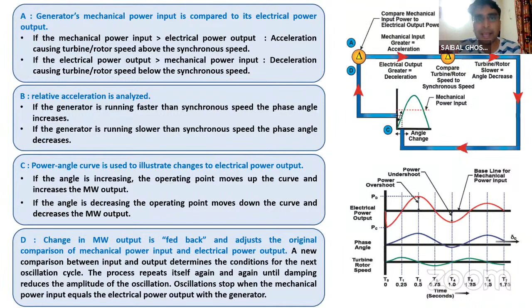At a certain point of time, electrical torque is more than mechanical torque. At another point of time, mechanical torque is more than electrical torque, and so on. So this basically constitutes the oscillations, and to damp the oscillation, we need to bring these torques together again, and for that we have these PSS.